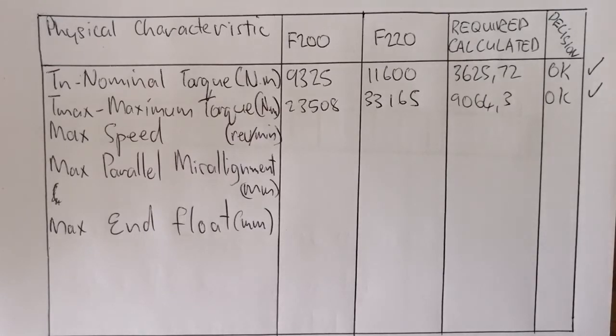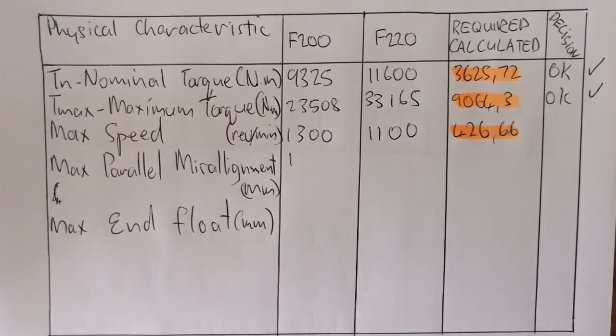Next, maximum speed. One can see that the speed it can handle for the F200 is 1300, for the F220 is 1100. What we've calculated or what the coupling needs to run is 426.66 RPM. Therefore, okay.